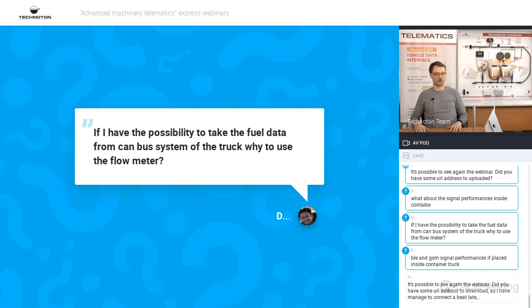That's the difference. Another example is when the data isn't available - or rather it is available, but corrupted. Recently we had a project where the total fuel used counter in the CAN bus was corrupted, showing dozens of millions of units of fuel used by a bus, which is obviously not possible. In that case the data was not usable, even though it was available for reading. So the flow meter is the only option to get real fuel consumption in that case.